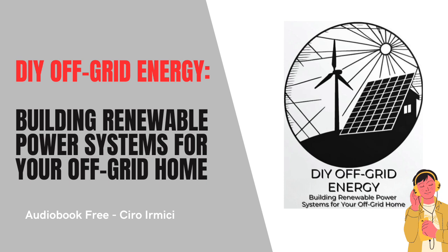Battery issues such as low charge levels, voltage imbalances, or reduced capacity are also common in off-grid setups. If your batteries are not holding a charge, it could indicate a problem with your charging sources, battery degradation, or excessive power consumption. Testing individual batteries for voltage and capacity, as well as checking the state of charge regularly, can help identify failing batteries that need replacement.